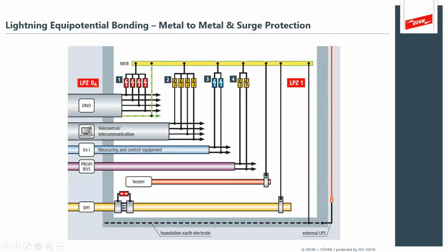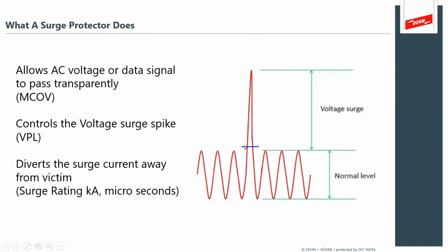Surge protection serves that purpose for your electrical connections. If you can't equipotential bond it, you have to equipotential surge protect it. And that's what's happening with your other lines. Your data and your power lines are being protected to that master bar. So it's essentially equipotential bonding for electronics. So what is it doing?